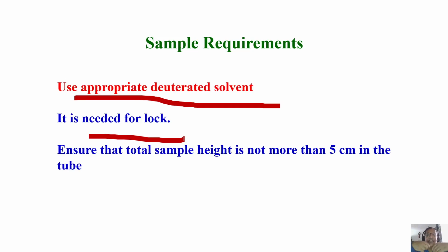Now, if you acquire the signal once again for co-addition of the data, and by then the field has drifted, your resonating frequencies are different. So you will get broad peaks or distorted spectra. You will not get high resolution spectra. Lines will be terribly broad and distorted.